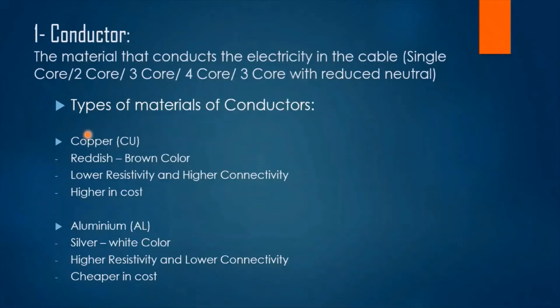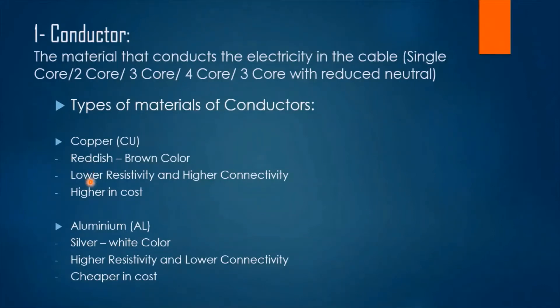The first layer is the conductor layer — the material that conducts electricity in the cable. It could be single core or multi-core. We have two types of conductor materials: copper and aluminum. Copper has a reddish-brown color while aluminum has a silver-white color. Copper has lower resistivity and higher conductivity, while aluminum has higher resistivity and lower conductivity. For example, if we have a load of 60 amps and select a copper cable, we would select a size of 16 mm².